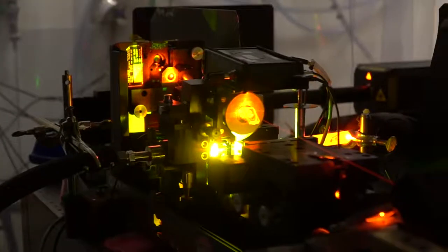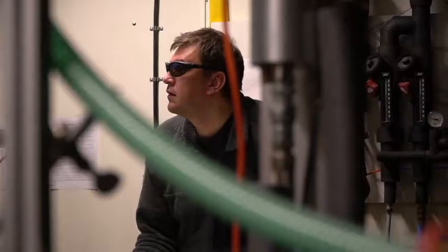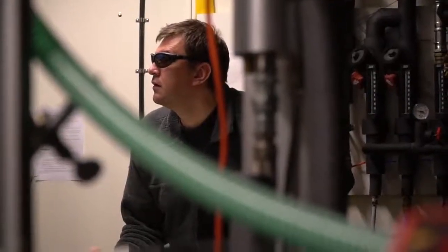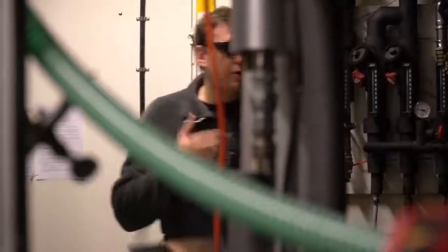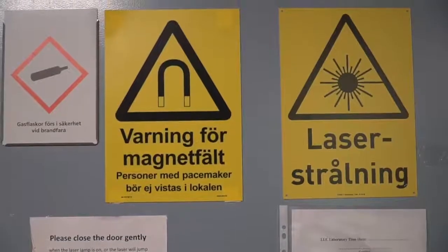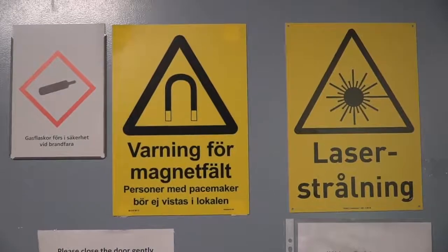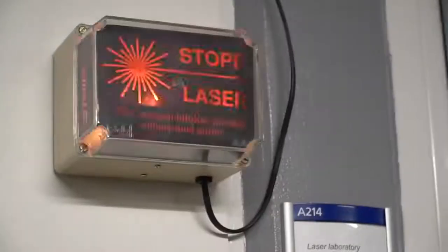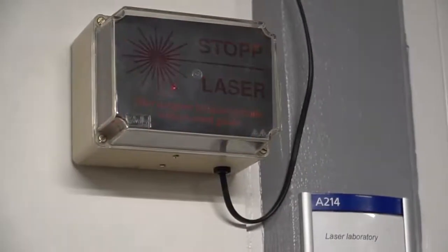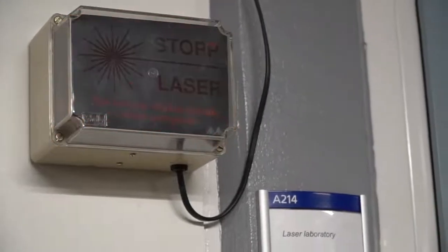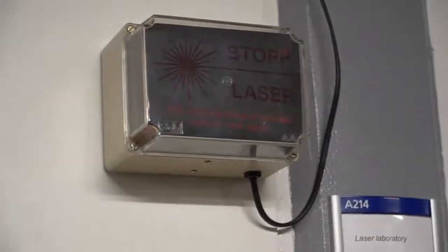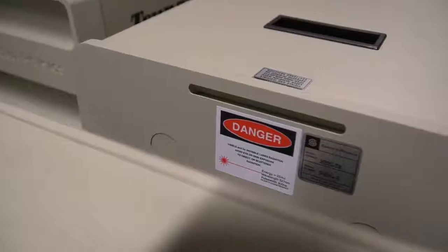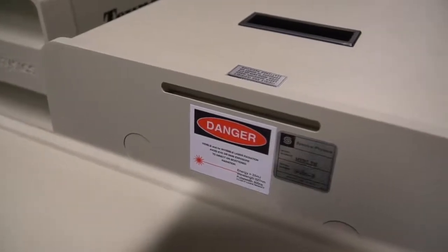For a safe working environment, there are some general rules that should be followed when working with lasers. You should make sure that the room is equipped with the correct warning signs prior to starting work, and always turn on the laser warning light if a laser is operational inside the room to alert others. Any lasers should be appropriately labeled with their class type and safety warnings.